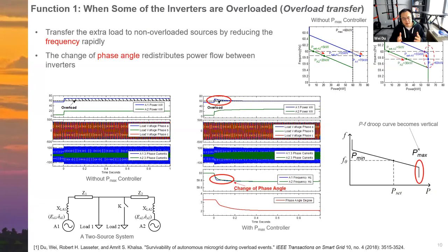So here are the test results with this Pmax controller enabled. You can see that for the same event, if we switch the load 2 on, both A1 and A2 first still increase their output power or current to meet this load change because they are just voltage sources. And then once A1 becomes overloaded, this Pmax controller is activated to reduce its frequency rapidly. During the transient, the frequency of A1 drops faster than the frequency of A2. So this frequency difference results in the change of phase angle, and the change of phase angle redistributes the power flow between the two inverters.